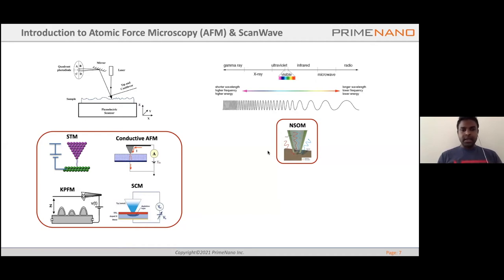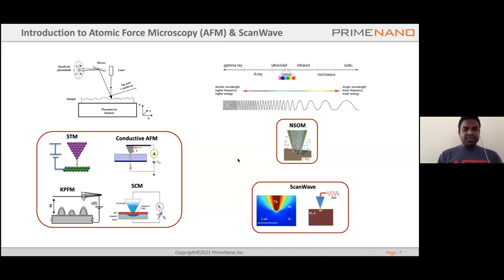of the sample. In ScanWave systems, we use microwave frequencies through this AFM probe, and we look at the reflections from the surface. And the reflections represent the impedance of the sample. Further, you can also apply other electrical bias, like in scanning capacitance microscope, you can apply an AC bias, and you can also look at the electrical depletion width or the modulation of the depletion width as you apply the voltage.